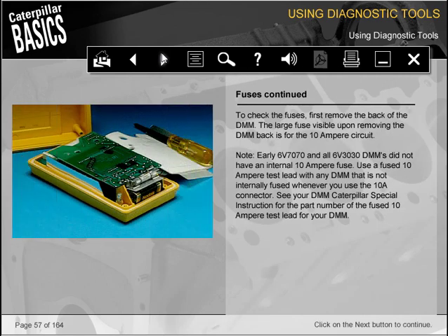To check the fuses, first remove the back of the DMM. The large fuse visible upon removing the DMM back is for the 10 ampere circuit. Note, early 6V7070 and all 6V3030 DMMs did not have an internal 10 ampere fuse. Use a fused 10 ampere test lead with any DMM that is not internally fused whenever you use the 10A connector. See your DMM Caterpillar special instruction for the part number of the fused 10 ampere test lead for your DMM.